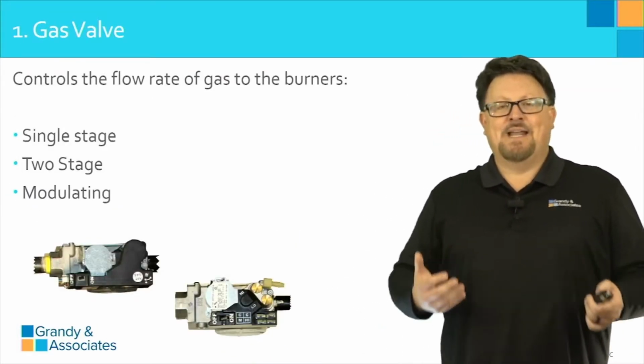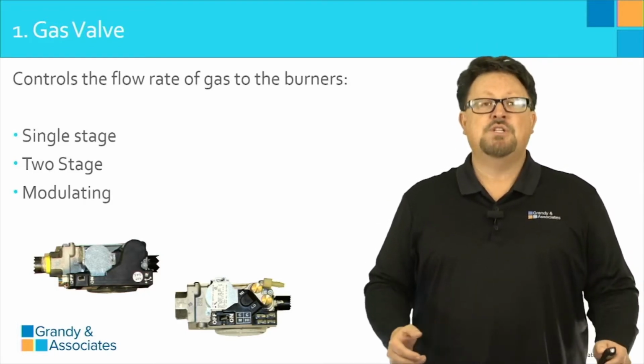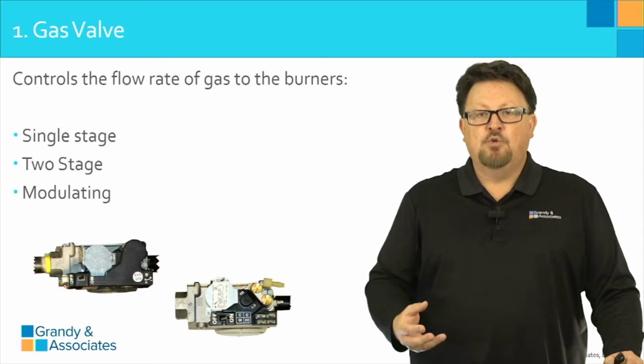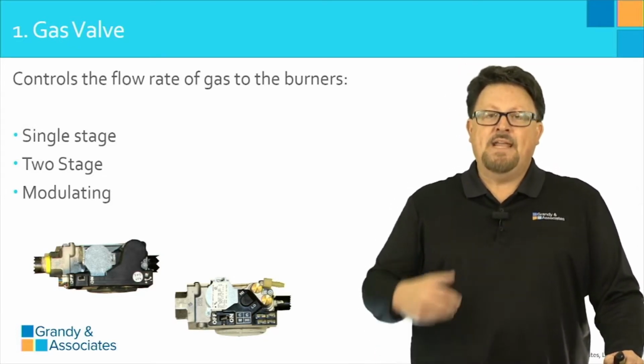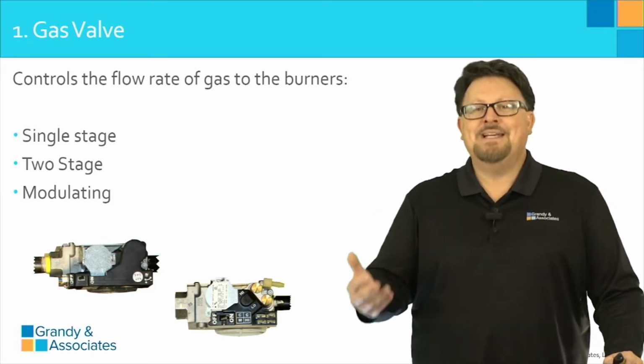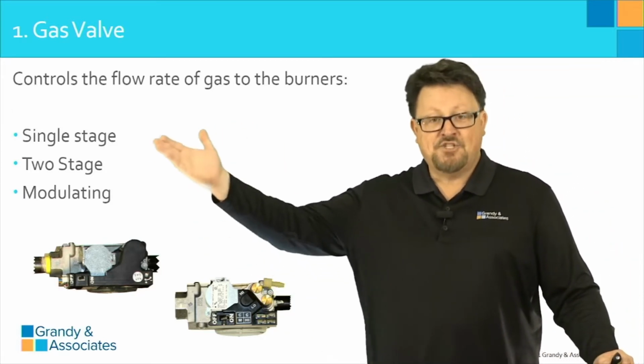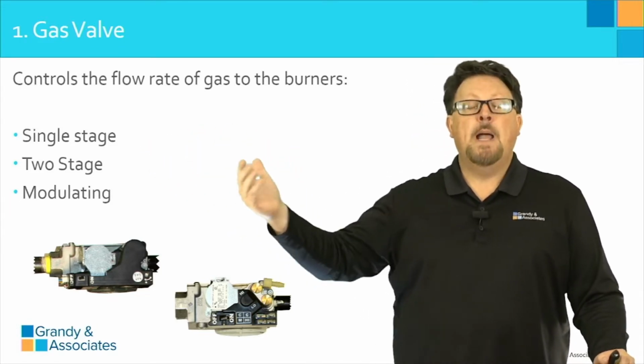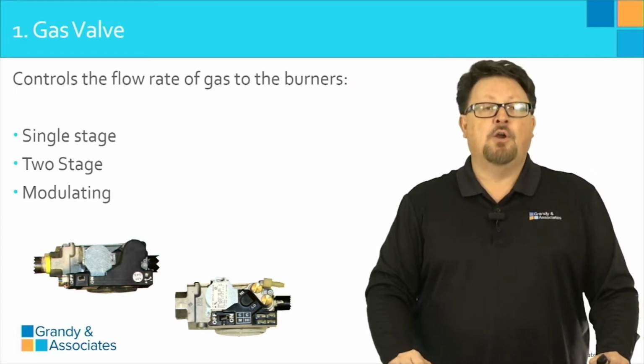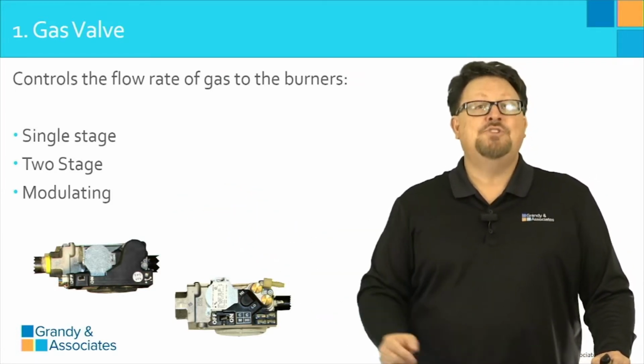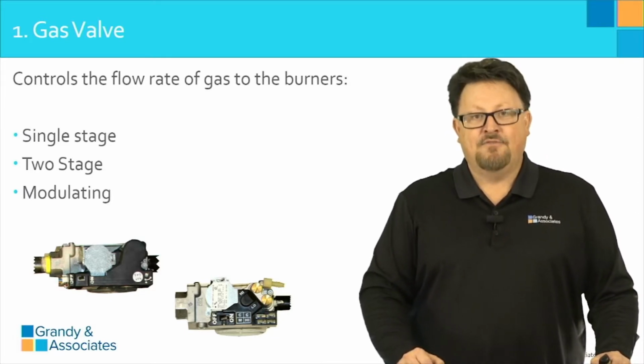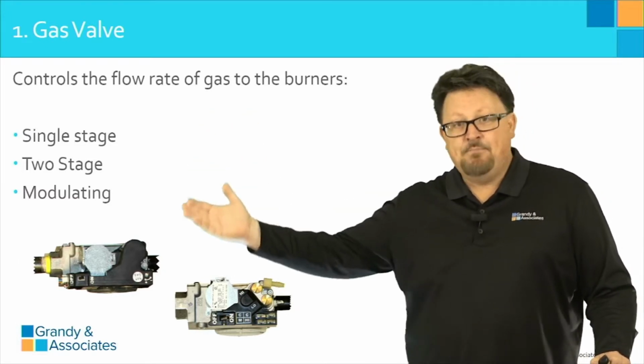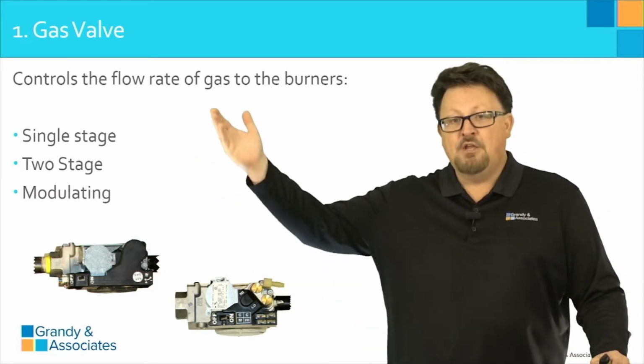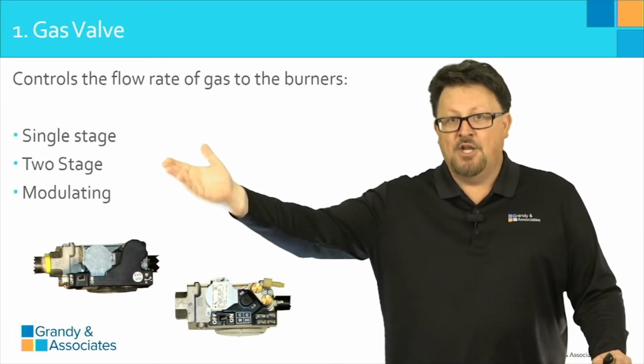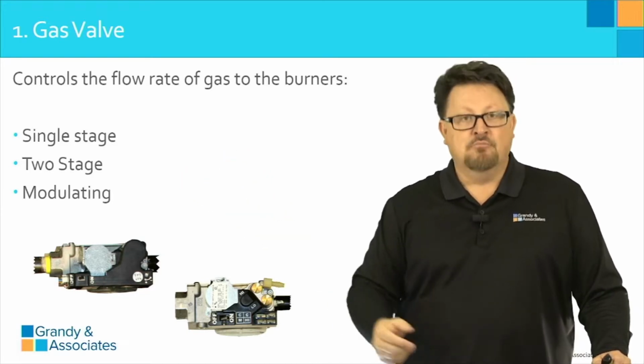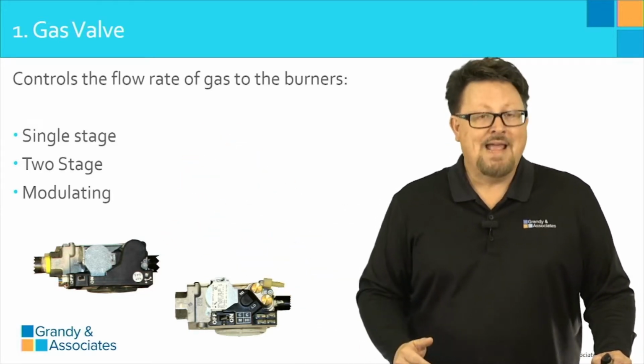What are the parts and pieces that allow the furnace to function properly? Well, one of those is the gas valves. They control the flow rate of gas to the burners. Now, the gas valves come in 3 dominant styles in the industry today. They can be single stage, 2 stages, or modulating. Many of the most efficient, most popular, highly efficient furnaces in the market have up to 60 stages on their modulating furnace operation. So there literally is a perfect fit for every customer. Someone looking for a more basic operation, someone looking kind of in the middle, and someone who is looking for the absolute most efficient furnace. There's an option for everyone.